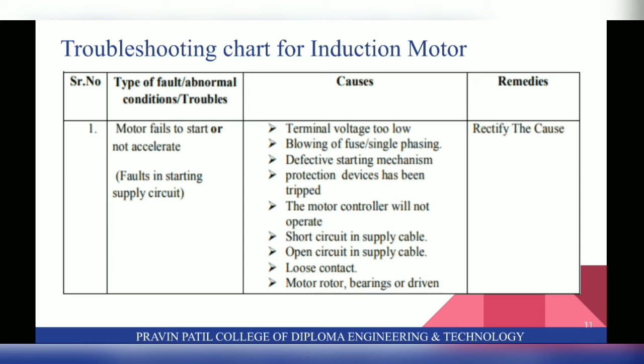If asked about squirrel cage induction motor, you have to add this point and inspect the rotor bar endings for squirrel cage, and if asked for slip ring induction motor, you have to add this point that in case of slip ring induction motor, check the rotor resistance circuit and control. And suggested correction for this is rectify the cause and find the solution.